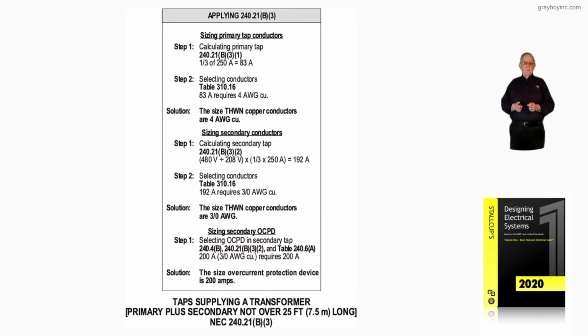Now this illustration deals with taps supplying a transformer. The primary, plus the transformer, plus the secondary conductors are involved here. And overall, it's 25 foot that we are looking at here from the tap to the primary of the transformer, through the transformer, to the secondary conductors terminated in the panel board. But we're applying 240.21(B)(3) along with 240.21(C)(5), I believe it is.